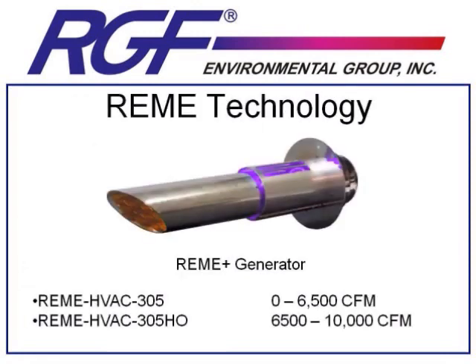REME technology currently comes in two separate sizes: a 0 to 6,500 CFM and a 6,500 to 10,000 CFM rating. Just like the PHI systems, if you're dealing with a job that is 40,000 CFM, you can just add units to total up to the 40,000 CFM you need — in this case, four of the HVAC 305HO. Also like the PHI system, if you are dealing with a high-load application like a smoker's bar or casino, you may need to up the size of the REME unit to overcome the extra load of pollutants in the air.